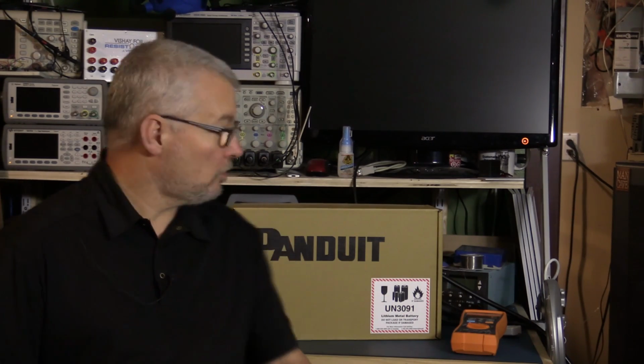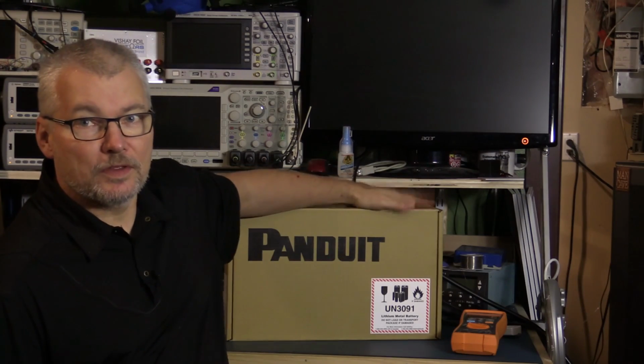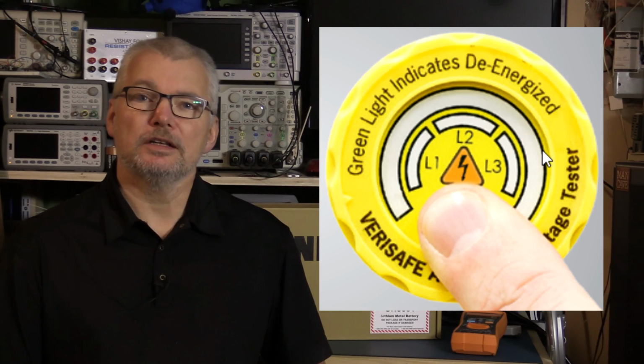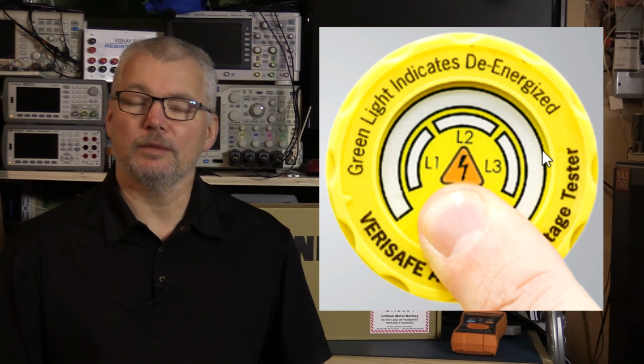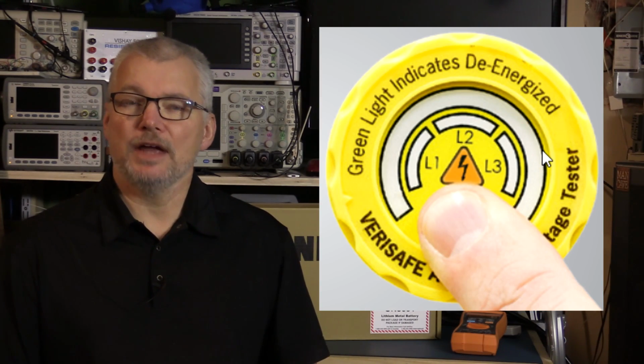Now, it's important, don't get me wrong, but it's one of those areas where a lot of people get tempted to cut corners. So to battle that, a company called Panduit has come out with a device you can install in the panel that gives you an indication on whether the panel is powered down or not, and it can significantly reduce the amount of time it takes to do these tests.